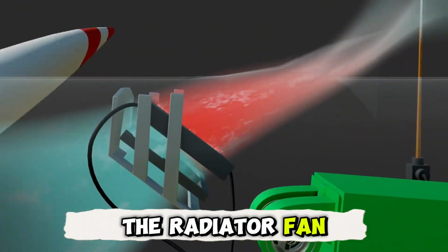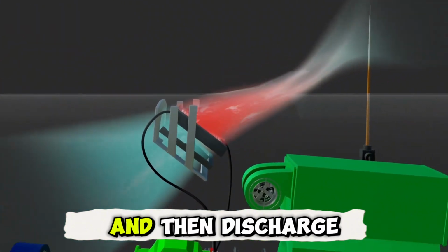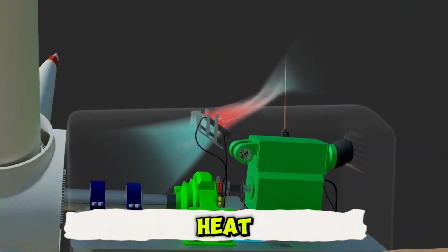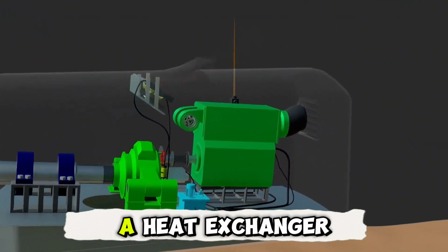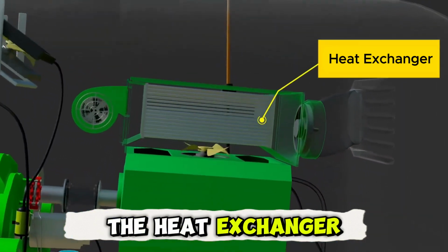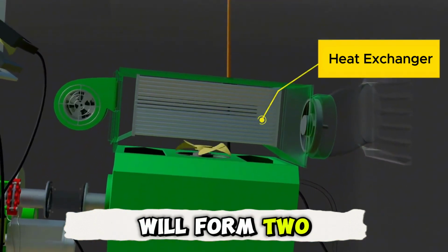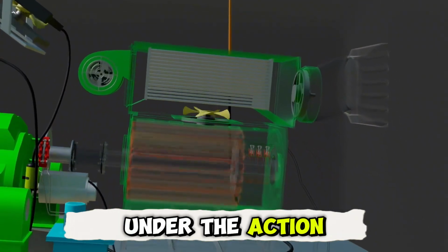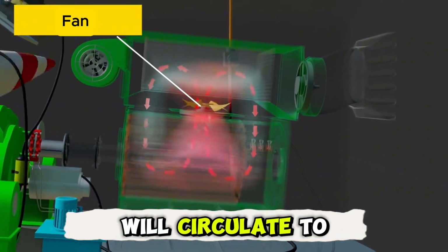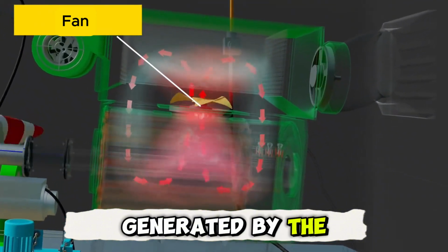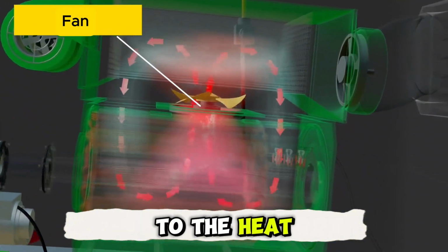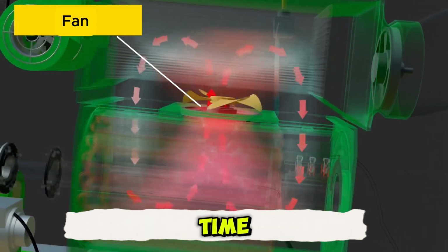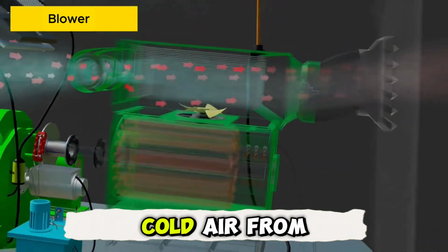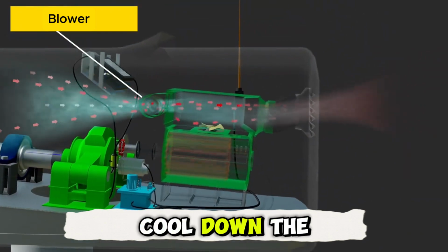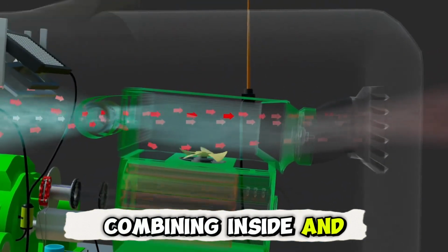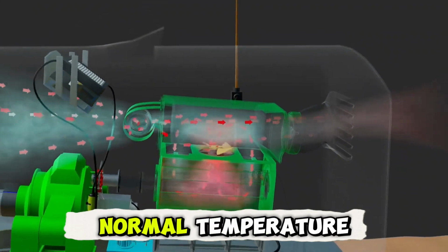The radiator fan will suck in air from the inside and then discharge it to the outside to dissipate heat. As for the cooling of the generator, a heat exchanger is used. The heat exchanger and the generator will form 2 independent air circuits. Under the action of the fan, the internal air will circulate to absorb the heat generated by the generator's windings and then flow to the heat exchanger for cooling. At the same time, the blower will also suck in cold air from the outside, which can also cool down the generator. Combining inside and outside ensures the generator works at a normal temperature.